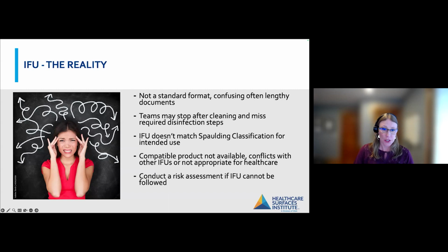And then as Linda mentioned earlier, sometimes the Spaulding Classification doesn't match the intended use for the IFU. So one example that comes to mind is our instruments that are used on eyes. A lot of times, like when you're going in and having your eyes checked, a lot of those pieces of equipment, the IFUs tell you to use a disinfectant, but it's a low-level disinfectant. It doesn't meet the high-level disinfection standard that it should. So that puts the healthcare provider and facility in a challenging position. So what happens when you can't meet that IFU?